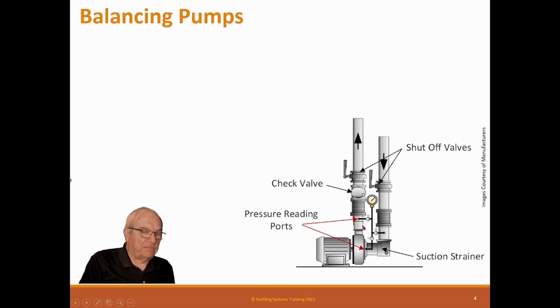When you go to balance a pump, we need a reading on the discharge of the pump here, and we need a reading of the suction of the pump here. So we can't have them out here. Now, you see here we have one here, but this is designed to close this valve and open this valve and take a reading before the strainer and take a reading here at the pump. Then you can get the differential pressure across the strainer to tell if it's dirty. Need to know if you need to clean it.